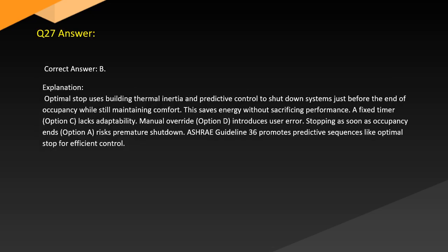Answer. Correct answer: B. Explanation. Optimal stop uses building thermal inertia and predictive control to shut down systems just before the end of occupancy while still maintaining comfort. This saves energy without sacrificing performance. A fixed timer, option C, lacks adaptability. Manual override, option D, introduces user error. Stopping as soon as occupancy ends, option A, risks premature shutdown. ASHRAE Guideline 36 promotes predictive sequences like optimal stop for efficient control.